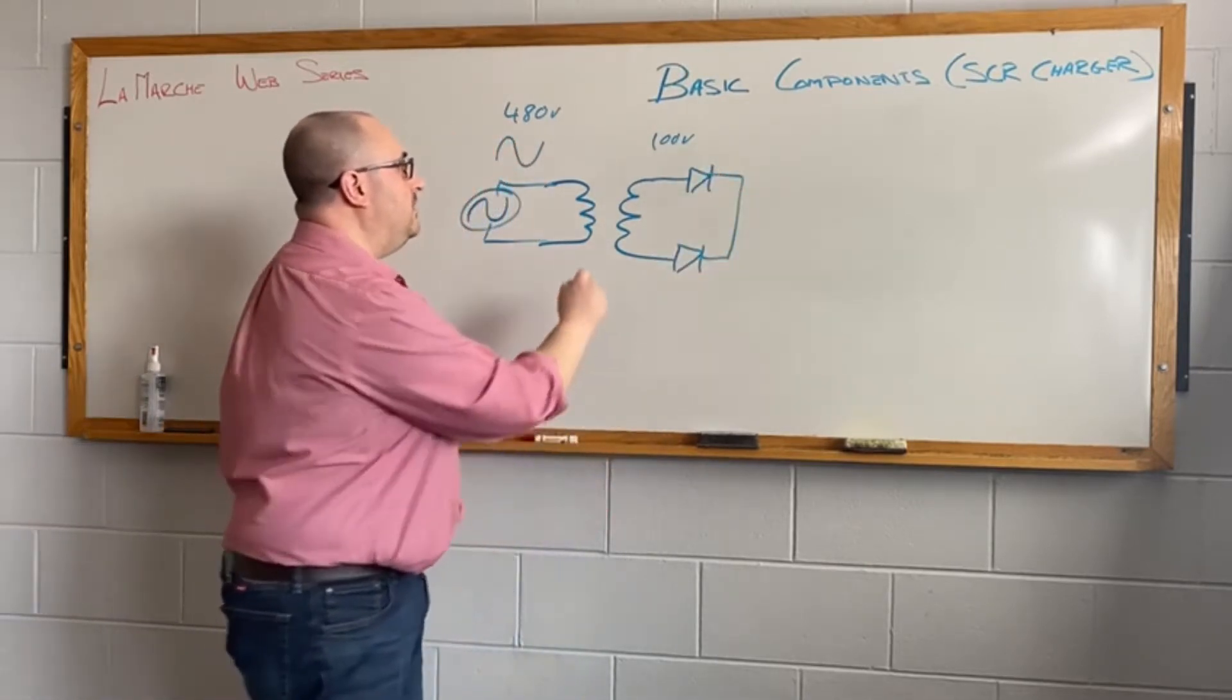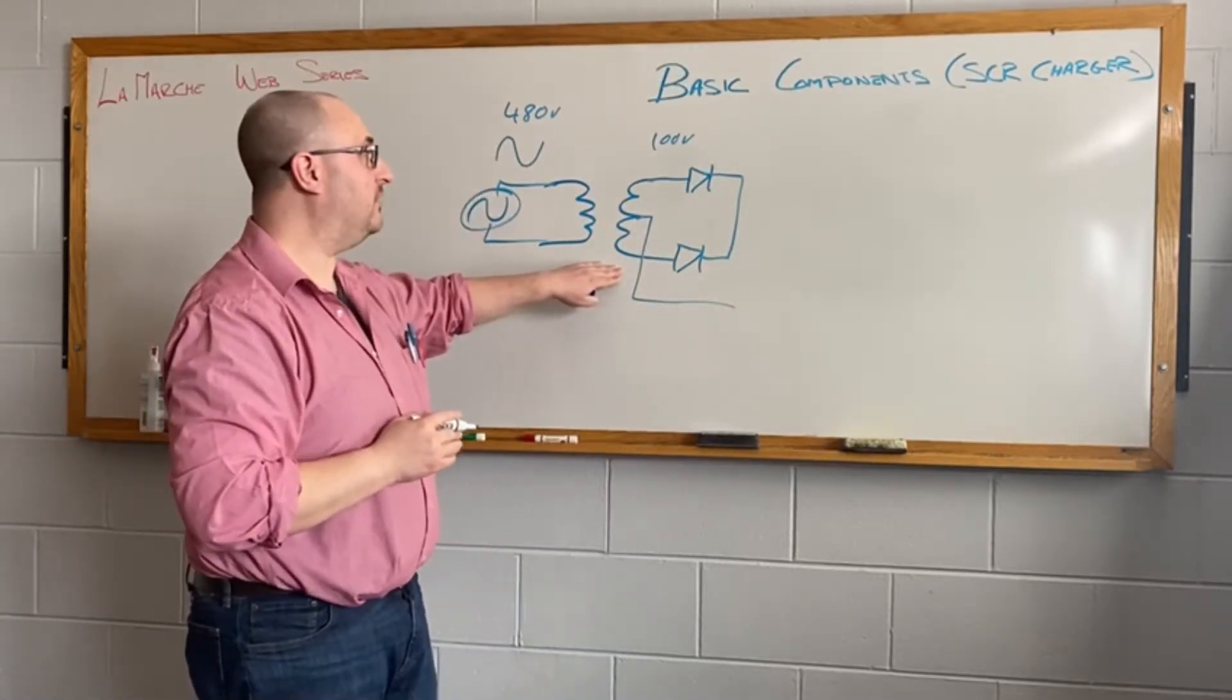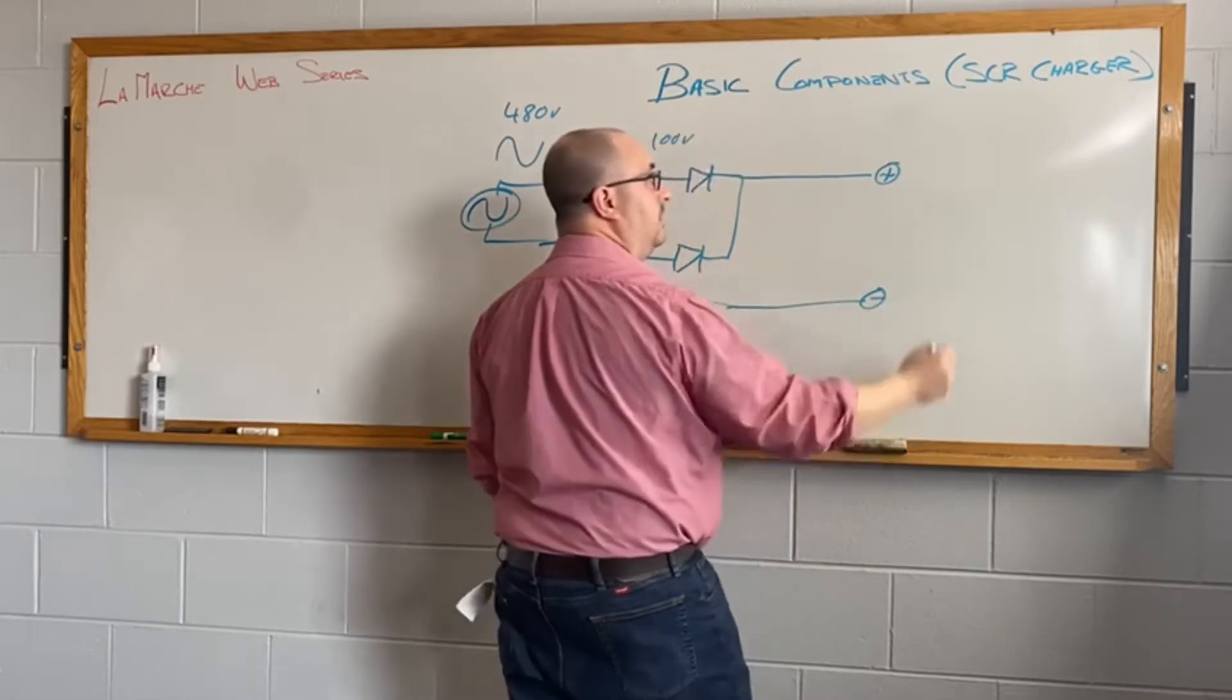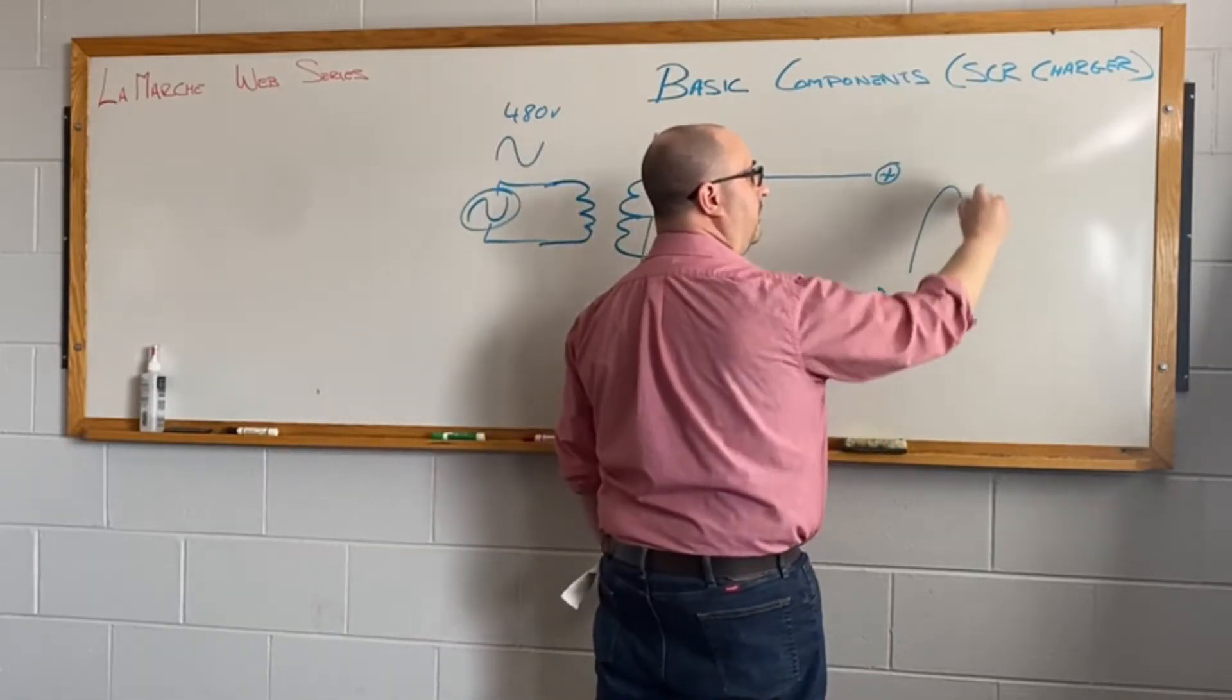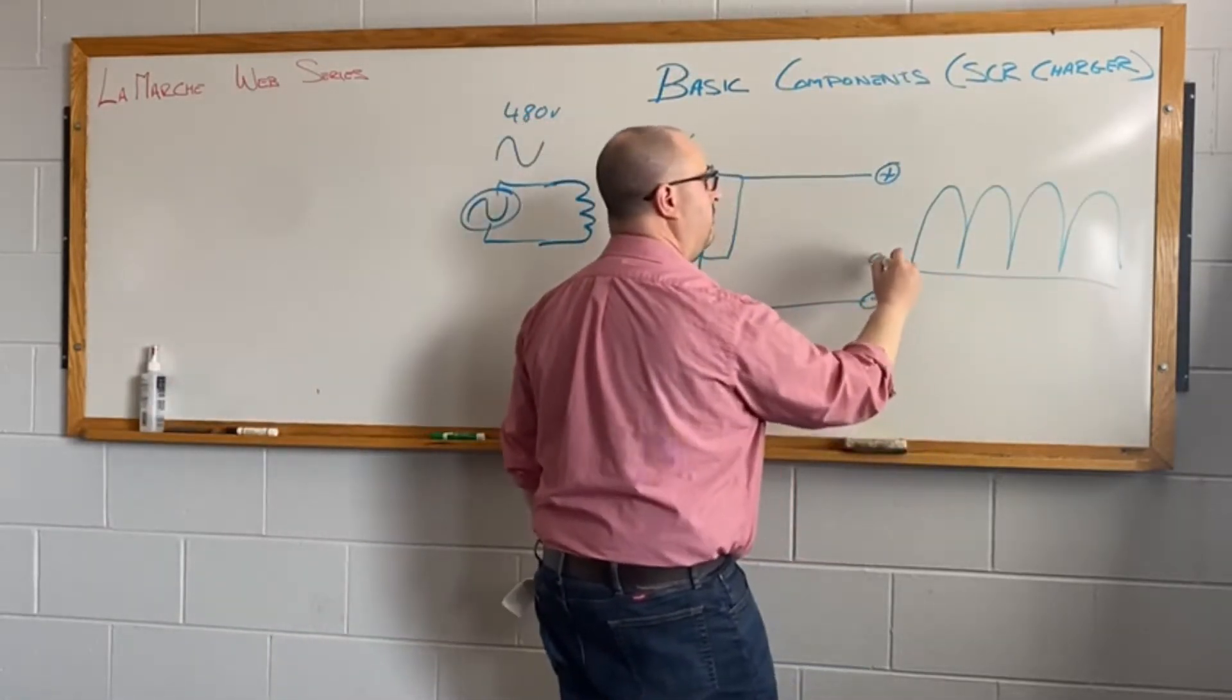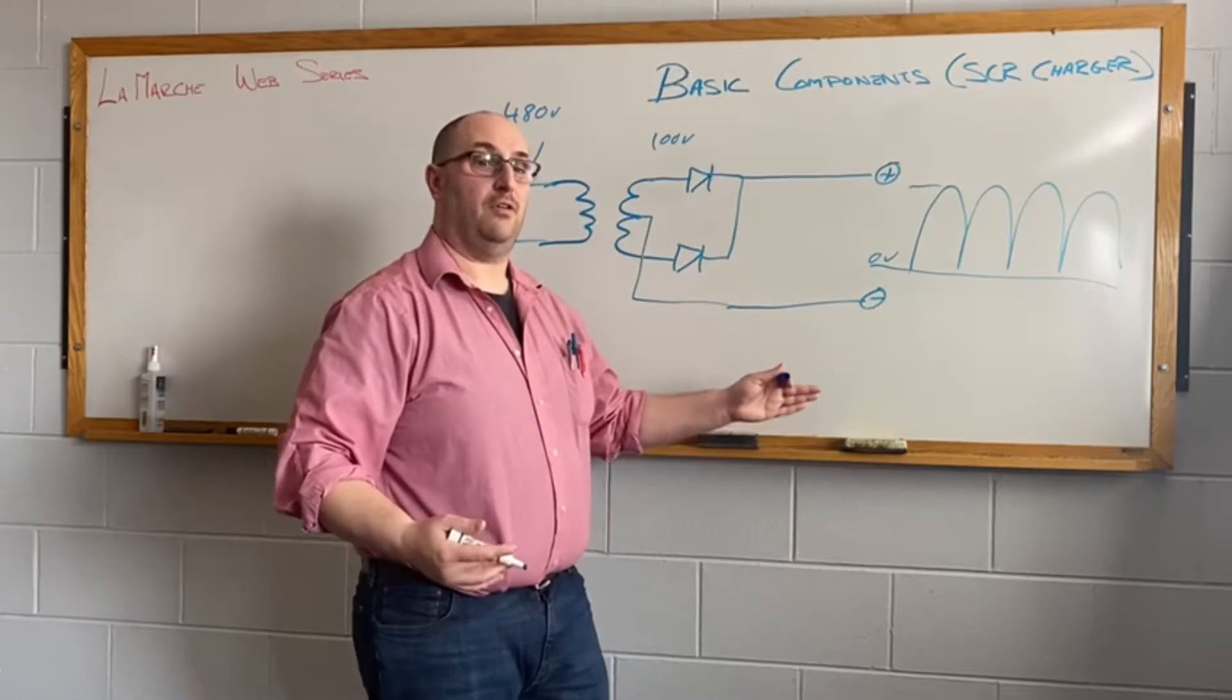So we need to be able to rectify this, and to simplify it, I'm just going to draw a center tap style rectifier. From this, you can get a plus and minus, and the resulting output waveform would be DC. But you notice that there's a high amount of ripple on this and this is not really a healthy thing for the battery.